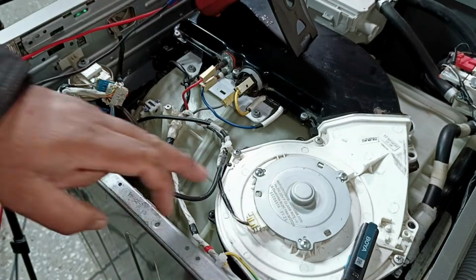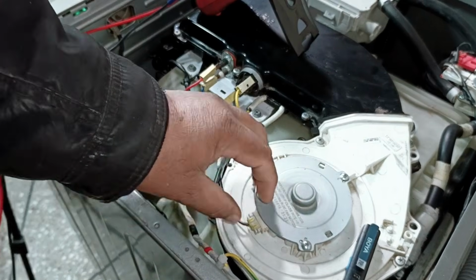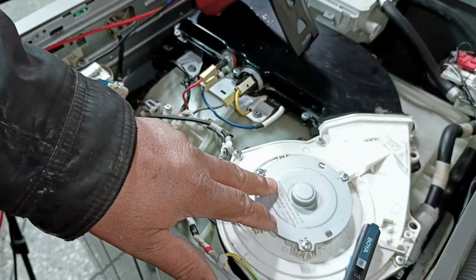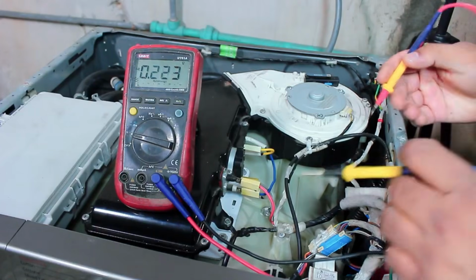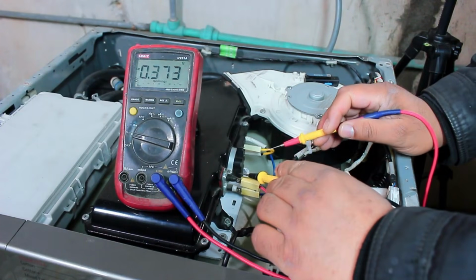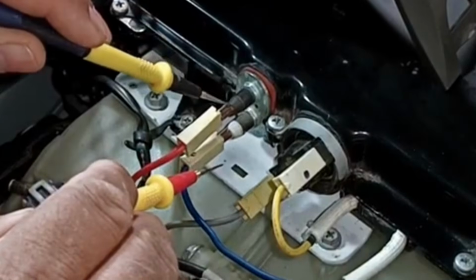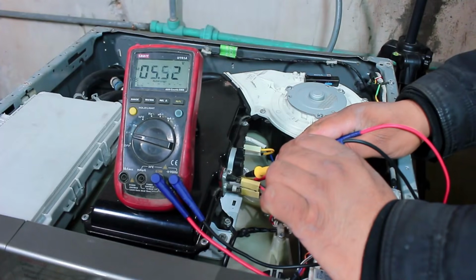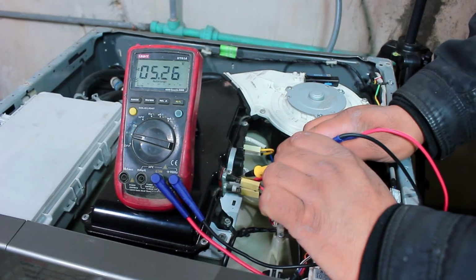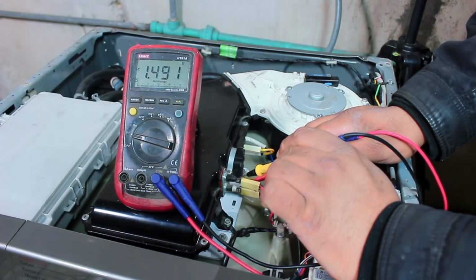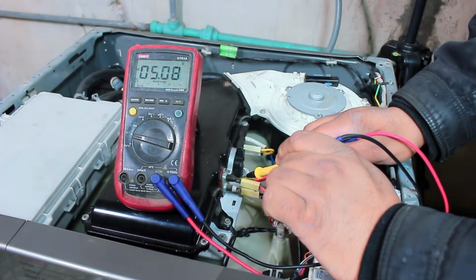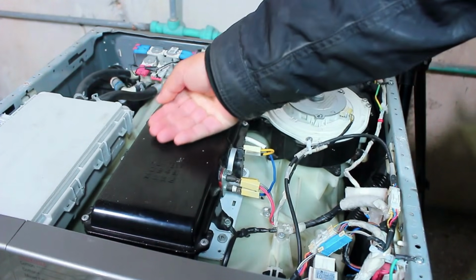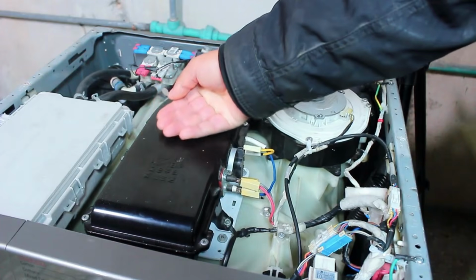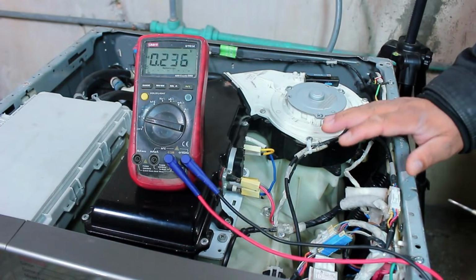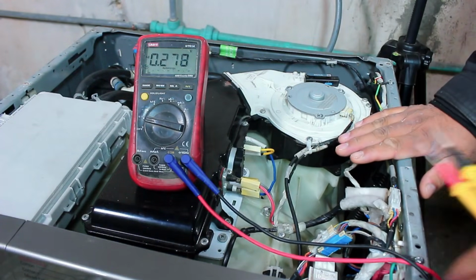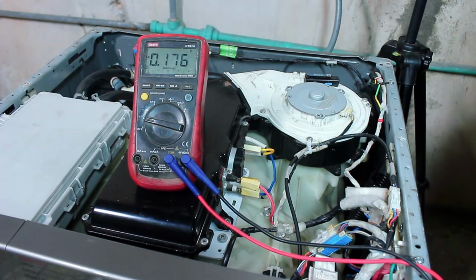As you can hear, the fan has started. I can clearly hear its sound. After a short while, the heating element should also turn on. Now I will check whether it has turned on or not. Now, I will check how much voltage is coming to the heating element. At the moment, there is no voltage present here. That means the system has not yet supplied power to the heating element. If we touch it carefully, we can also feel that the heating element is still not warm, so we need to wait for a short while. Once the system activates the heating element, we will be able to understand the situation clearly.